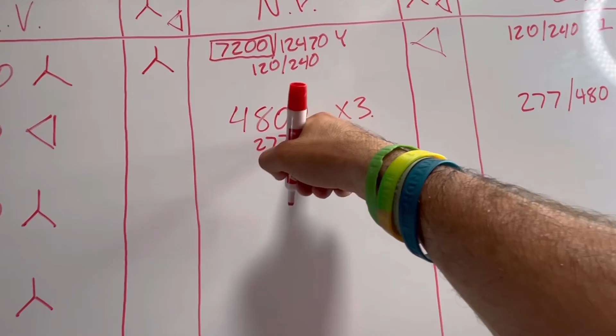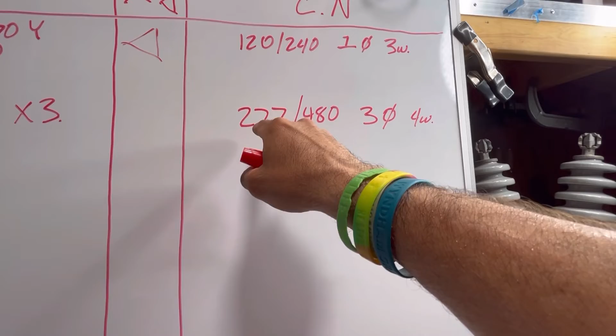Secondary side, right? We've got to determine our secondary hookup. Customer needs determine secondary hookup, not the nameplate. So the little rule that we use, the little hack, delta divides, right? Does this divide evenly into each other? 277, does that divide evenly into 480? Obviously not. Therefore, it's not a delta. It is going to be a Y.